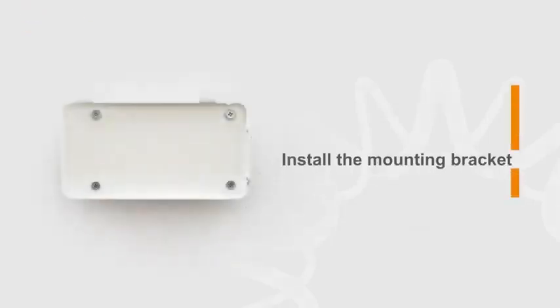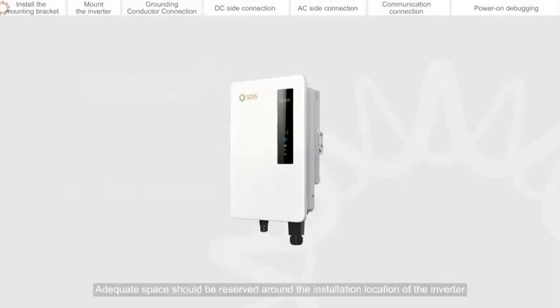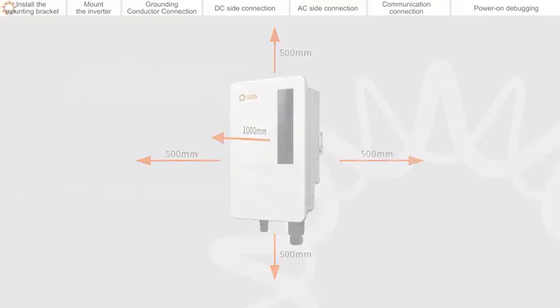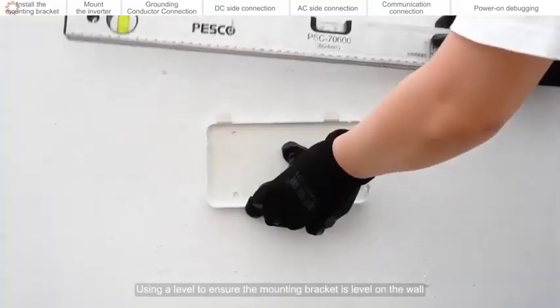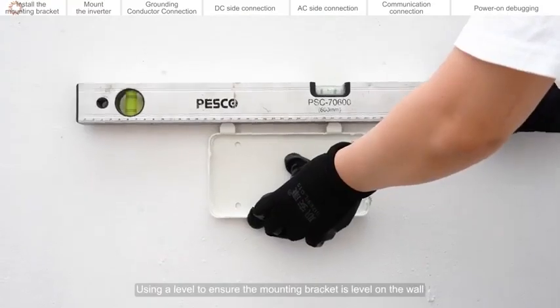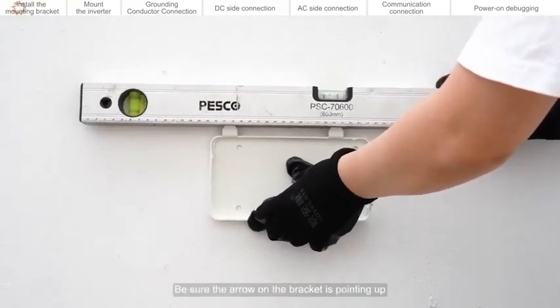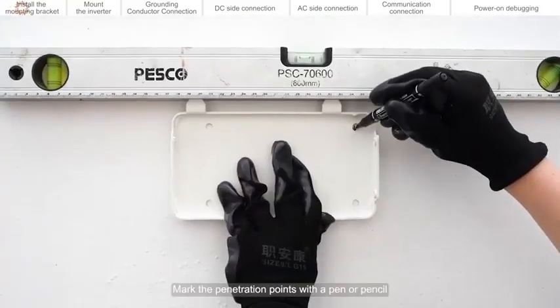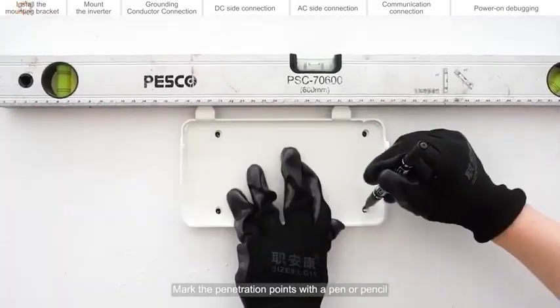Install the mounting bracket. Adequate space should be reserved around the installation location of the inverter. Using a level to ensure the mounting bracket is level on the wall. Be sure the arrow on the bracket is pointing up. Mark the penetration points with a pen or pencil.